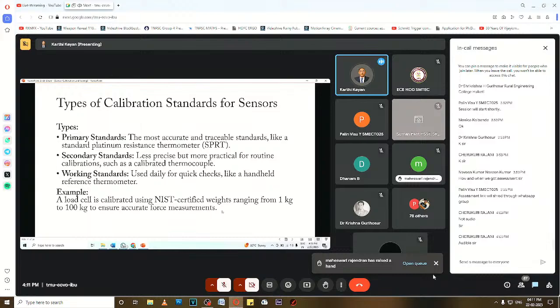The first one is the most accurate and traceable standard, like a standard platinum resistance thermometer. The second is secondary standards, less precise compared to primary standards but more practical for routine calibrations, such as a calibrated thermocouple. The third is working standards, which are used for daily usage.